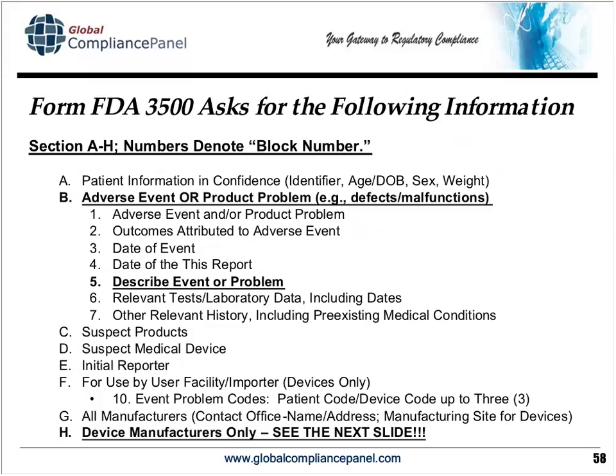Now, Form FDA 3500 asks for the following information. Well, we've seen the form briefly, but just to make sure that we understand. This event and problem code is straightforward. It can be easily followed. But again, describe event or problem. And please note that Section H is about device manufacturers only, so manufacturers have to fill out the section here. And regarding Section F for use by user facilities, there is a section about event problem code, patient code, and device problem code. You can provide up to 3, and if you need more, then you need to attach.